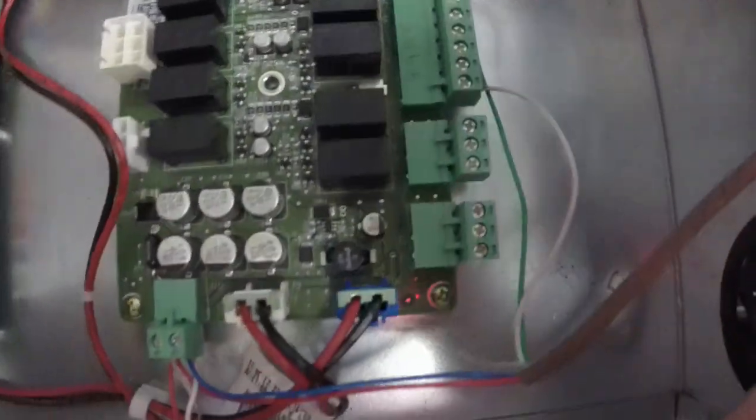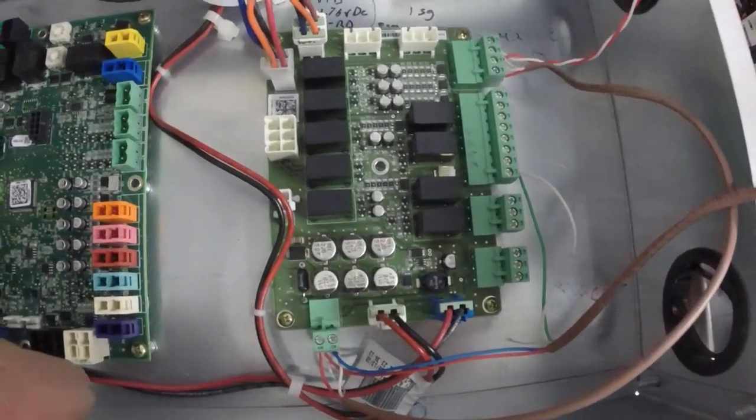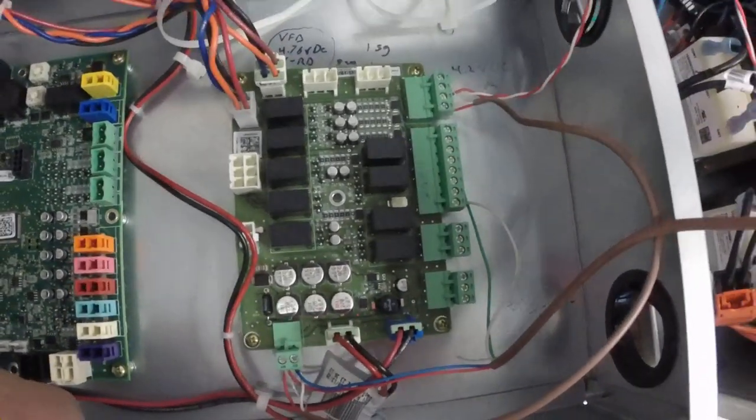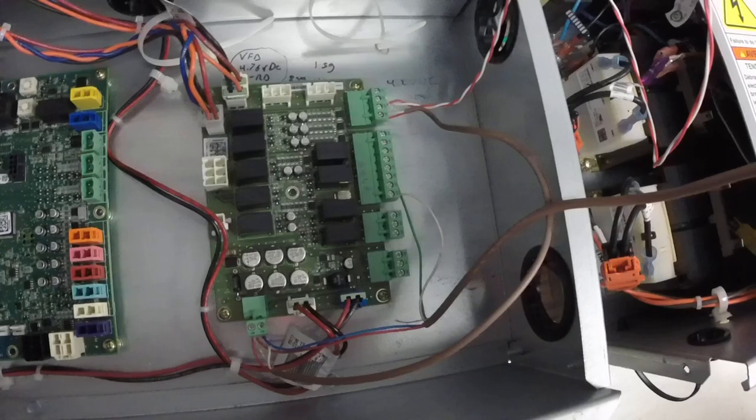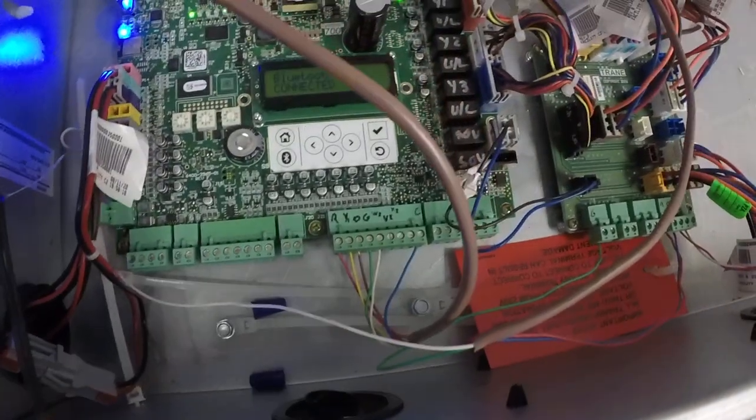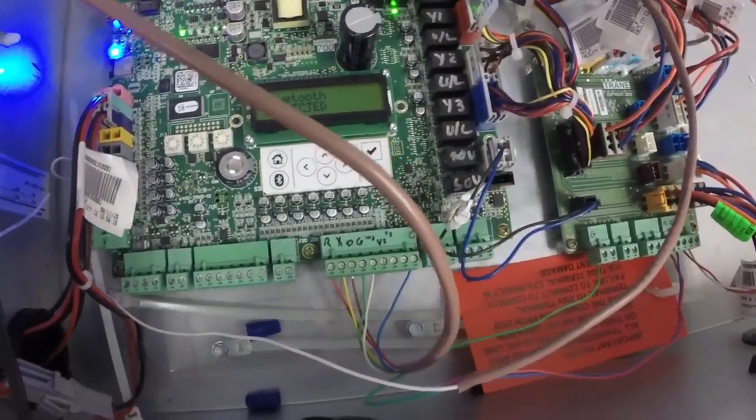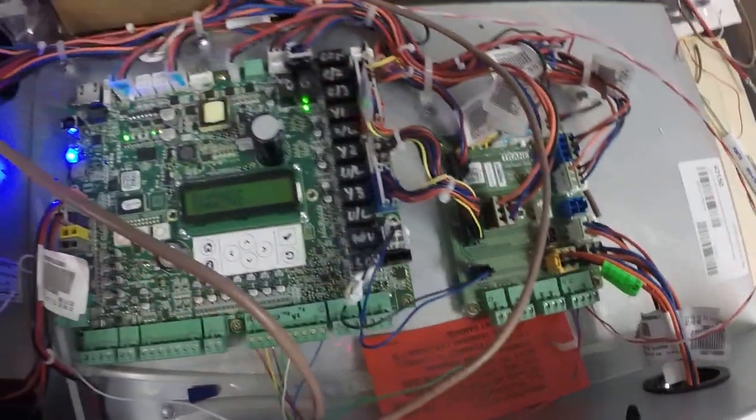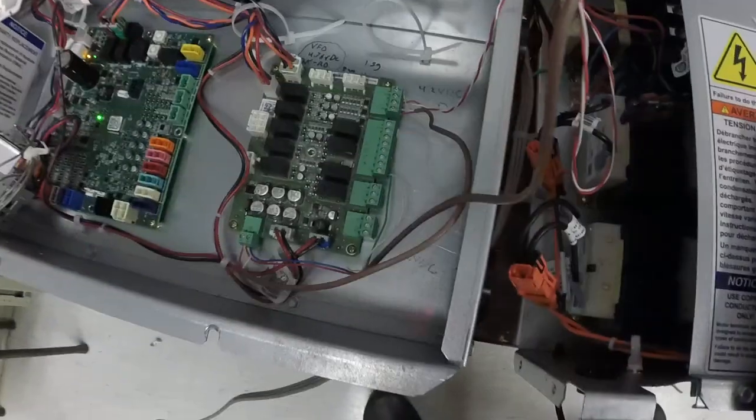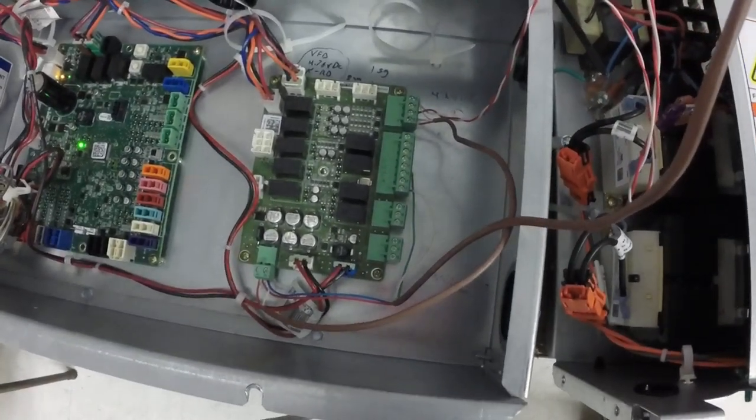And that's it. That's all for the communication portion of it. The connections in between the two units. So just remember thermostat runs to the outdoor unit, then your control wire from your outdoor unit runs from there to your air handler along with your twisted shielded pair.